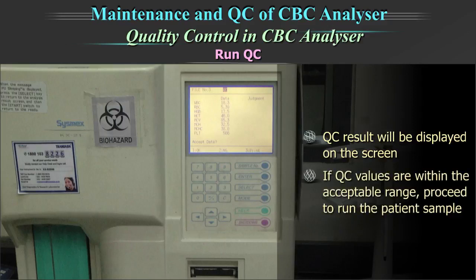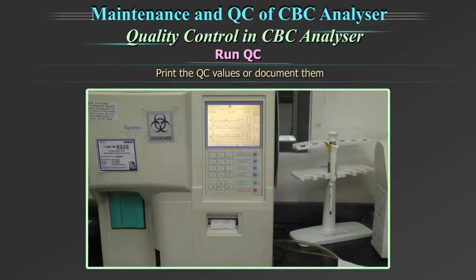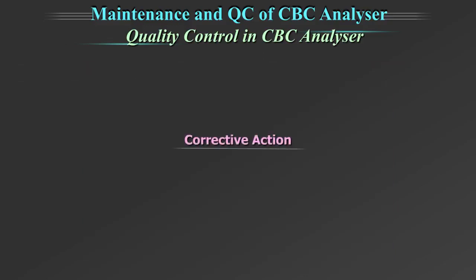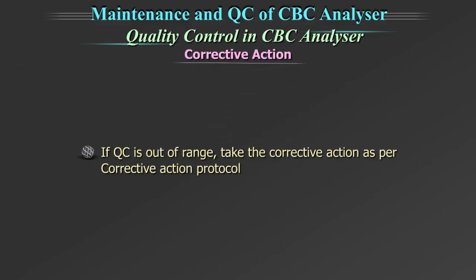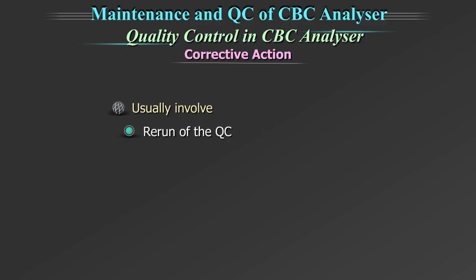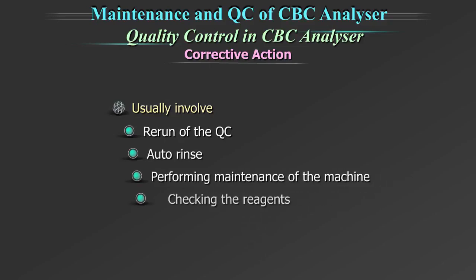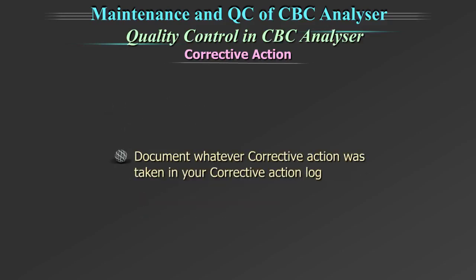If QC values are within the acceptable range, proceed to run the patient sample. Print the QC values and document them. The records of quality control should be stored for a year. Corrective action. If quality control is out of range, take the corrective action as per the corrective action protocol. This will usually involve rerun of the quality control, auto rinse, performing maintenance of the machine, checking the reagents and calibration if required. Document whatever corrective action was taken in your corrective action log.